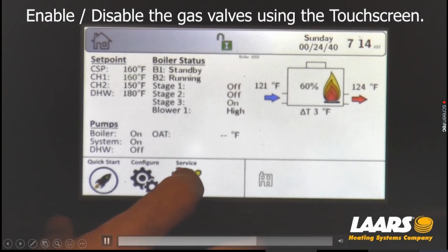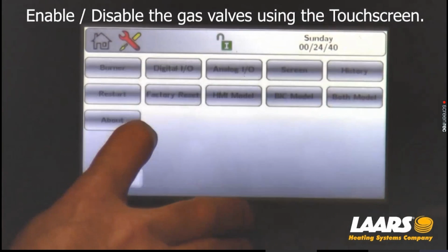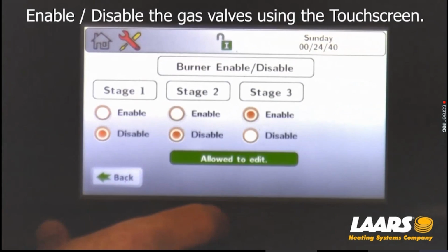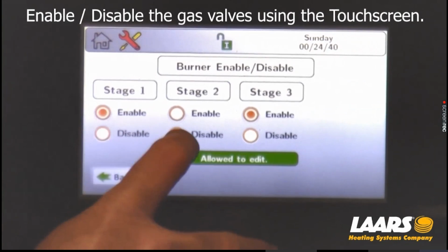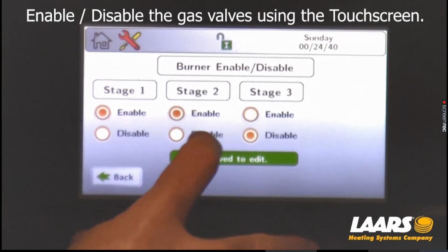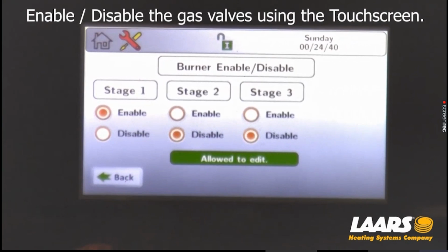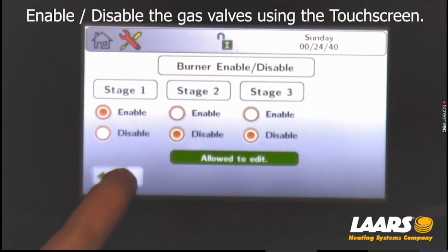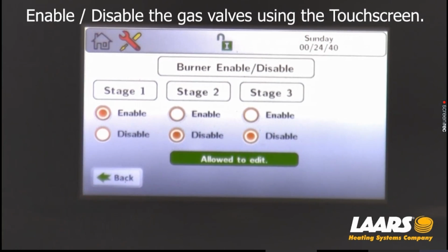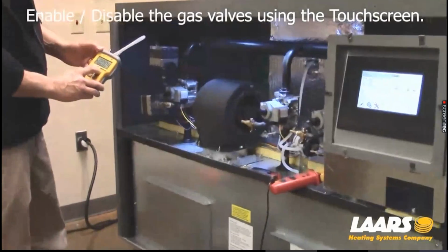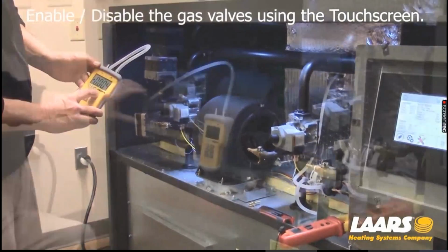So that is the example. Again, I'm going to go back in to burner. What I want to do is enable valve 1, and valve 2 and 3 I'm going to shut off in this example. And that way I can test manifold pressure on valve 1 with my digital manometer zeroed out.